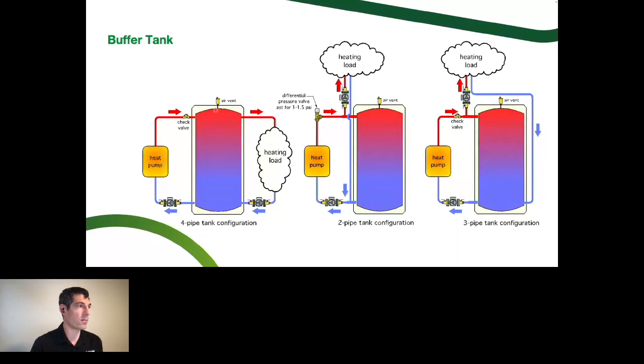So instead of being 140 at the top and 130 at the bottom, it's just a uniform temperature all the way throughout. And that could be kind of a problem because we like to stratify that tank and use the warmest energy for the longest amount of time so we don't have to fire the boiler. So that can work. I would say 4-port, 4-pipe tank configurations are a good fit if you have a reasonable delta T on both sides that's within 5 degrees or something like that. That might be a better way to go.